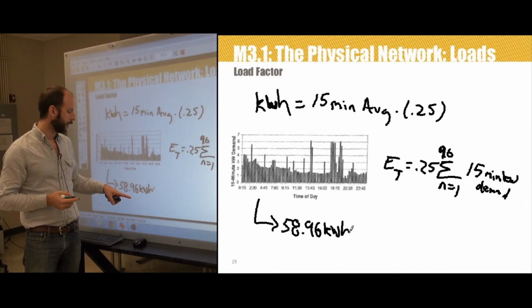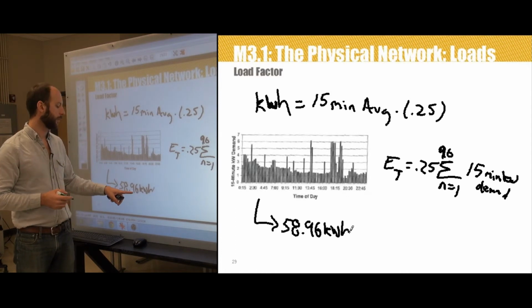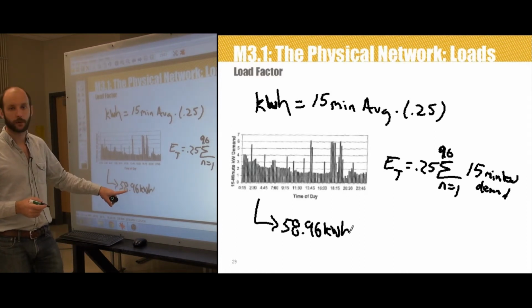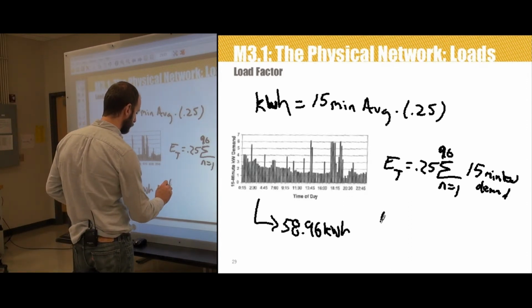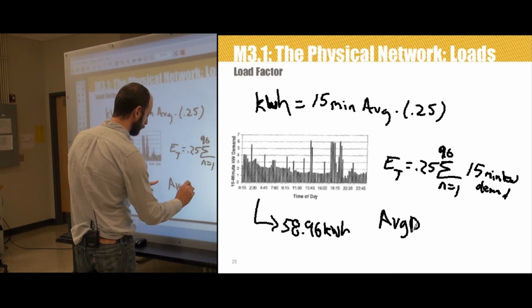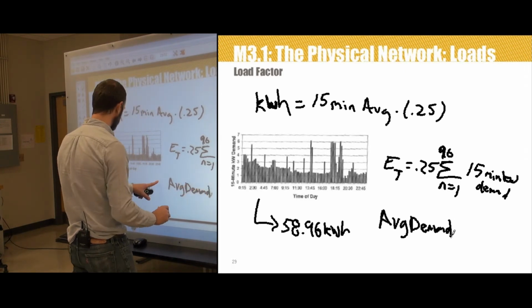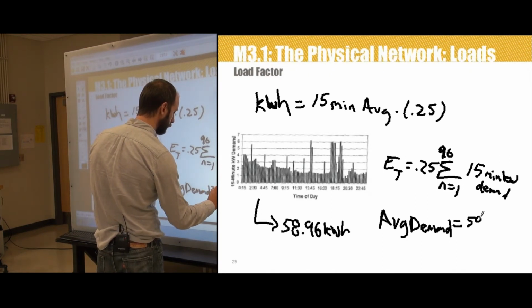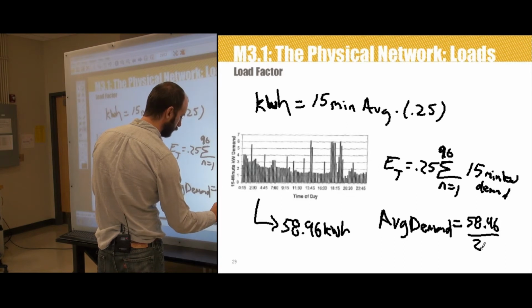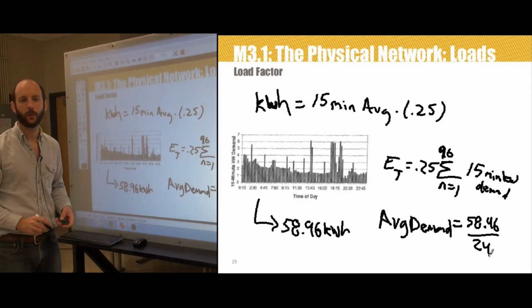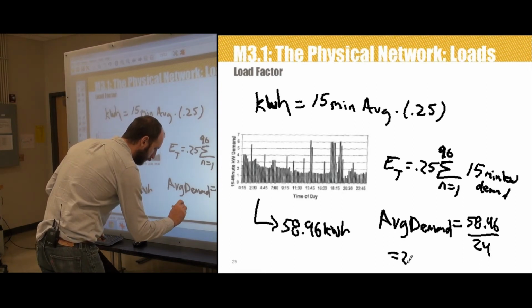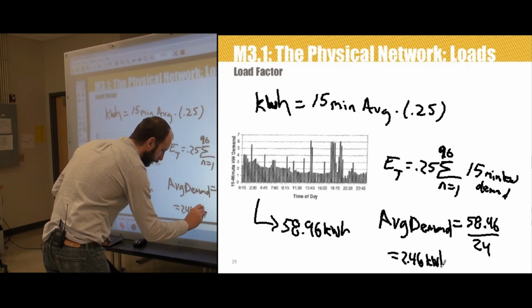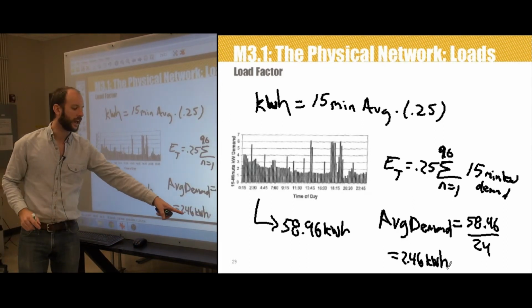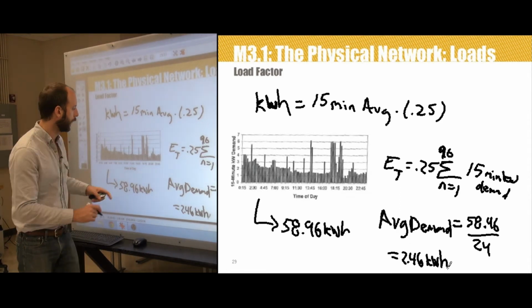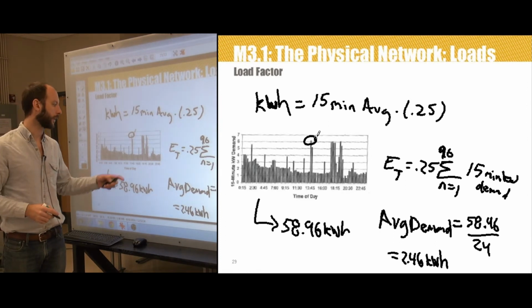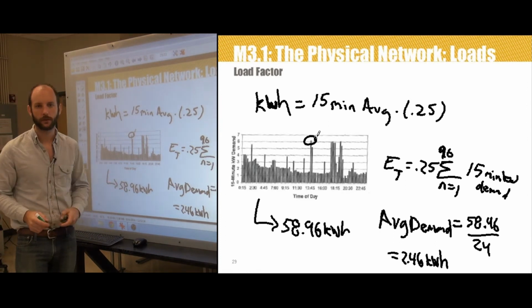We can then average this, right? That he used 58.96, or she used 58.96 kilowatt hours in 24 hours. So if I divide that number by 24, I'm going to get the average demand. It's going to be 58.96 divided by 24. And that's going to give me 2.46 kilowatts. So now I've got my 15-minute average, I've got my daily average, I've got my max 15-minute demand. I've got a lot of different things that I can begin to quantify consumer consumption behavior with.